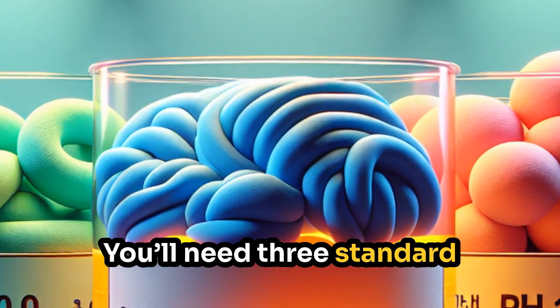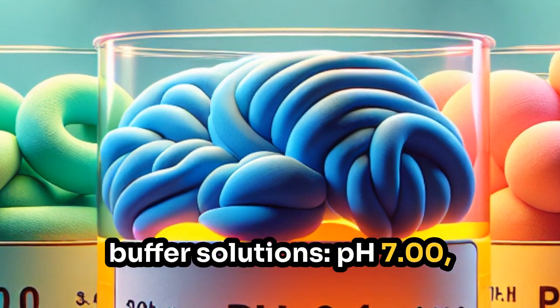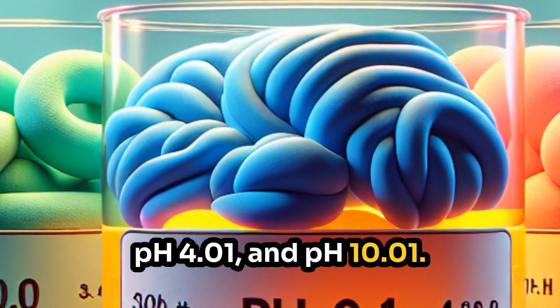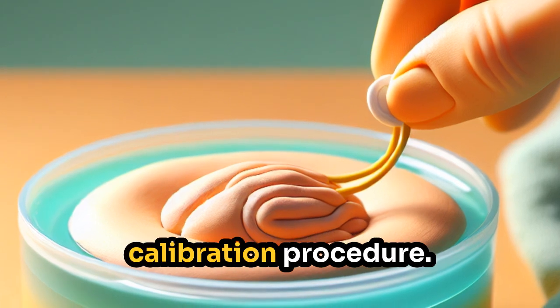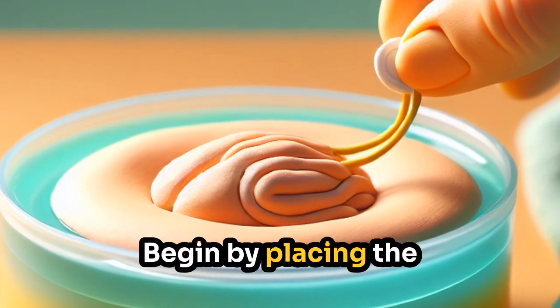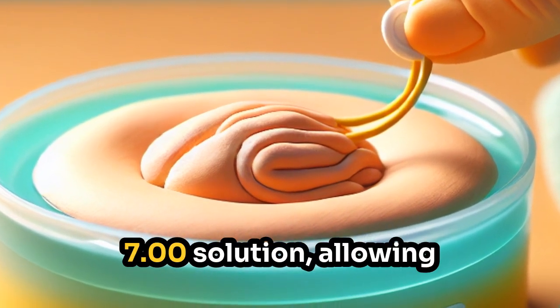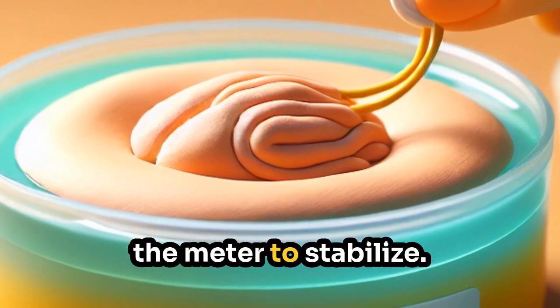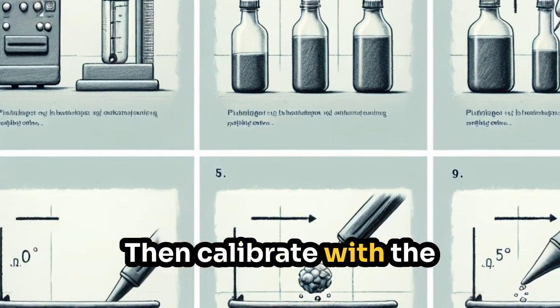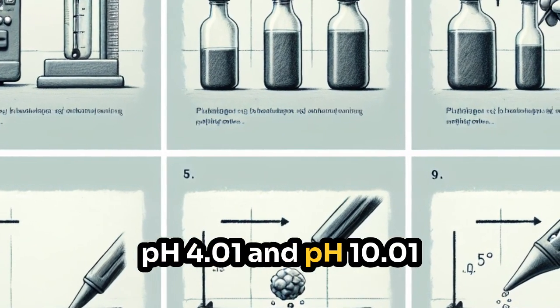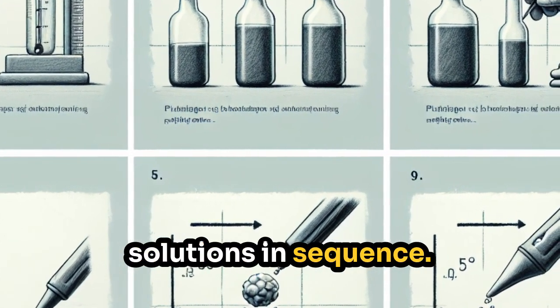You'll need 3 standard buffer solutions: pH 4.01, pH 7.00, and pH 10.01. Now start the calibration procedure. Begin by placing the electrode in the pH 7.00 solution, allowing the meter to stabilize. Then calibrate with the pH 4.01 and pH 10.01 solutions in sequence.